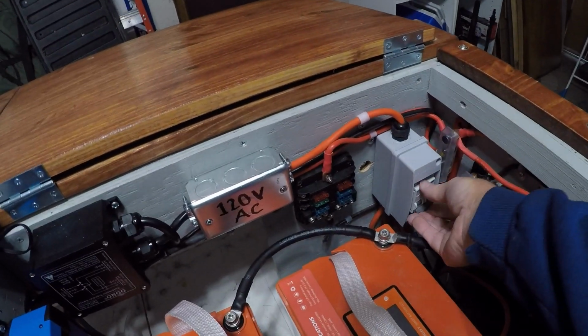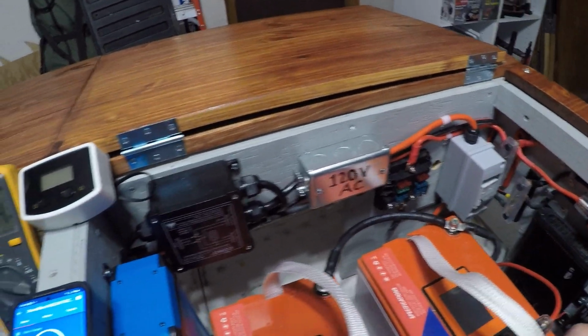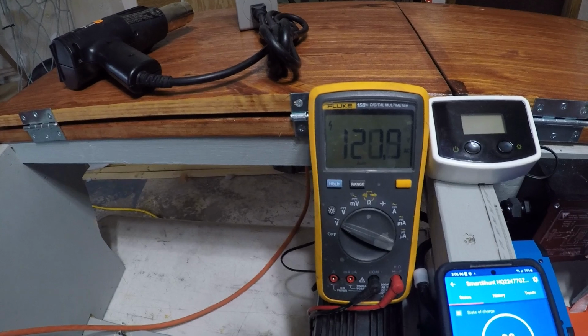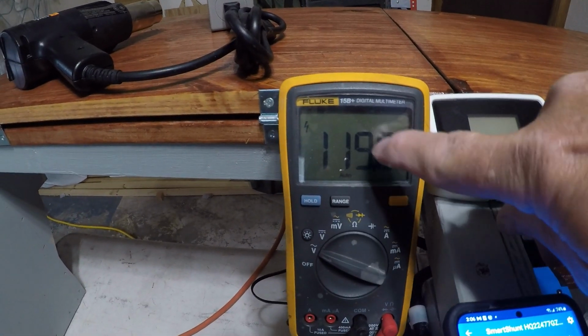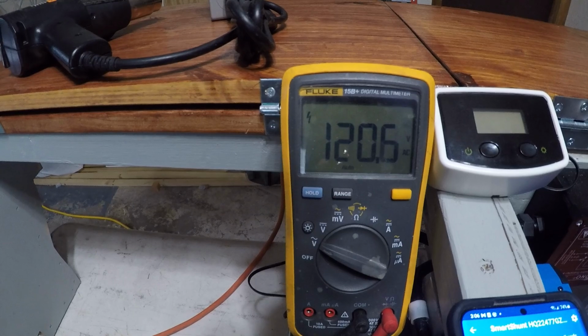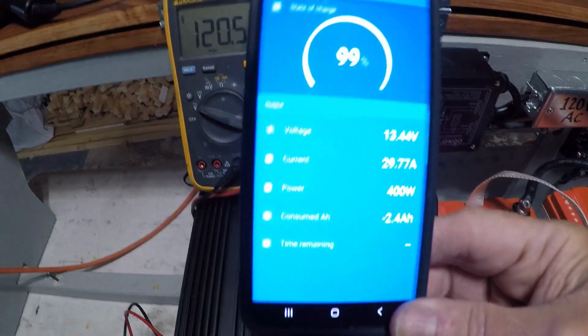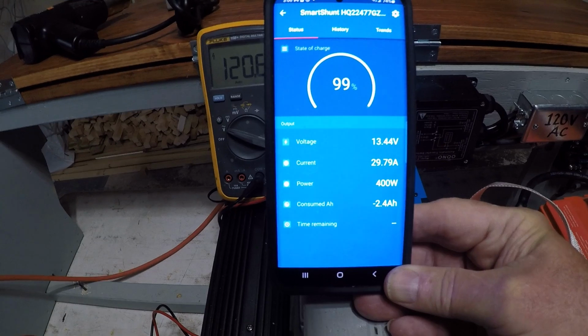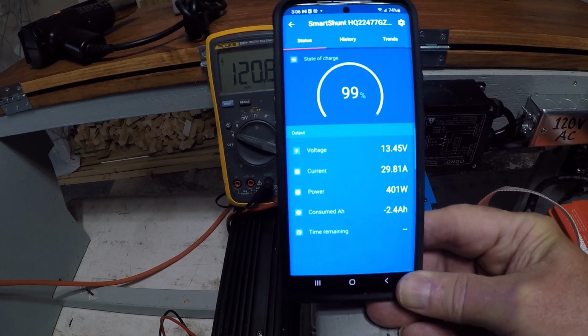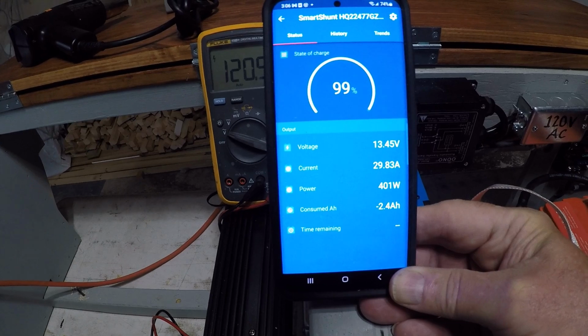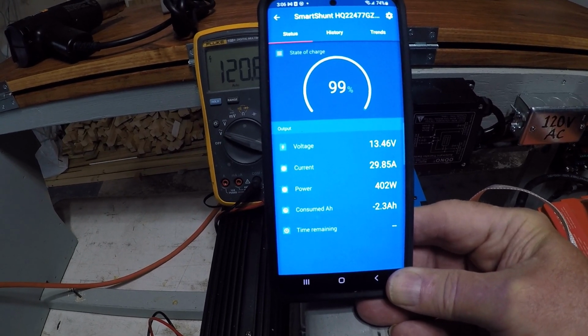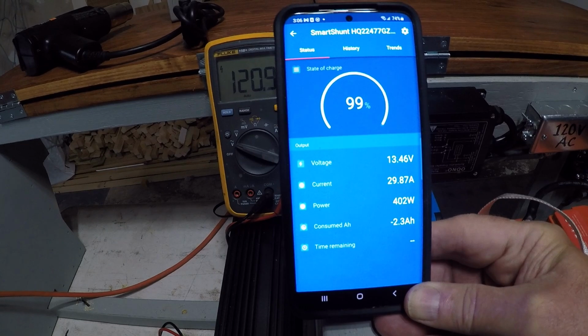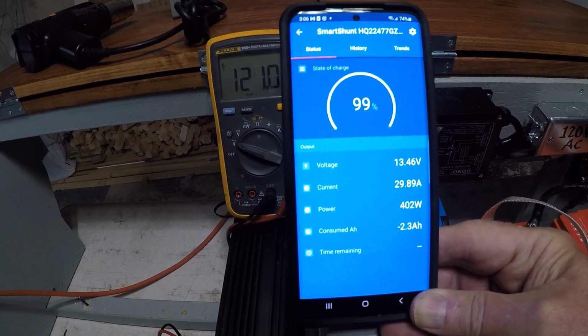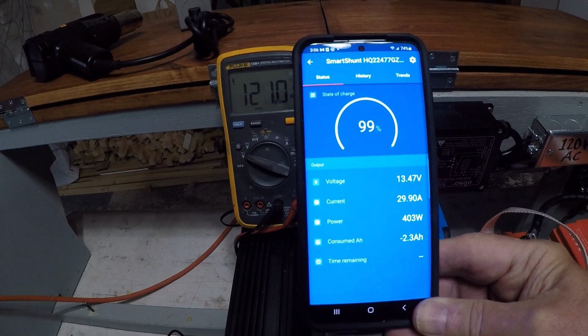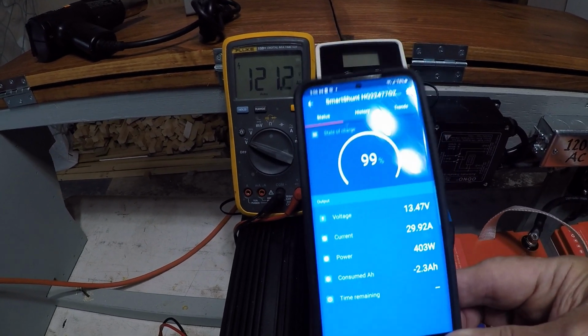So we'll come over here and turn on the circuit breaker. I heard a click. We now have 120 volts to our outlet, and the phone is showing me that the charger is working. Our battery voltage is 13.45 and it's charging at 29.84 amps. So right now the batteries are charging 400 watts worth. Our 30 amp charger is doing its job just like it's supposed to.